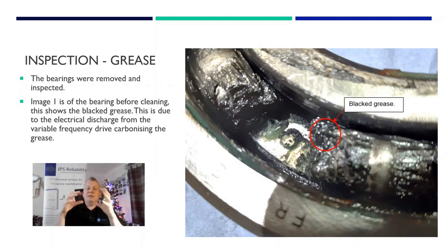Reason being is the high frequency noise should go back to your drive and then back to the transformer, to the earth. But it finds the easiest way out, and if you don't have the correct screening, earthing or protection, it builds up, and it just builds up like a capacitor and arcs through your grease and kills your grease. Right, what we'll do is we'll jump now and have a look at the bearing and some of the tools we use. Then we'll come back and finish off this part of the presentation. Okay.